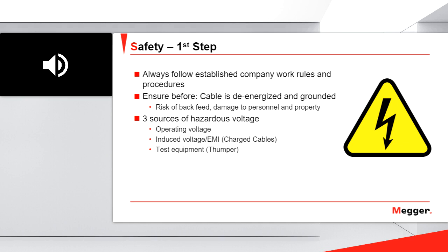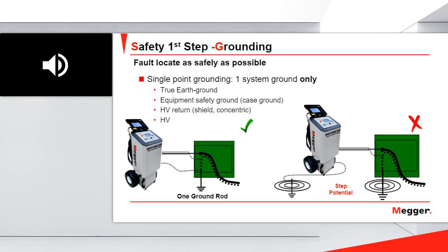And the last source of high voltage is the test equipment, the thumper. Okay, you could consider the thumper of the fault locator like a small substation that can generate lethal voltage. So this is something that you also need to keep in mind. So, continuing with the safety. As I said in the previous slides, the connection is very important.